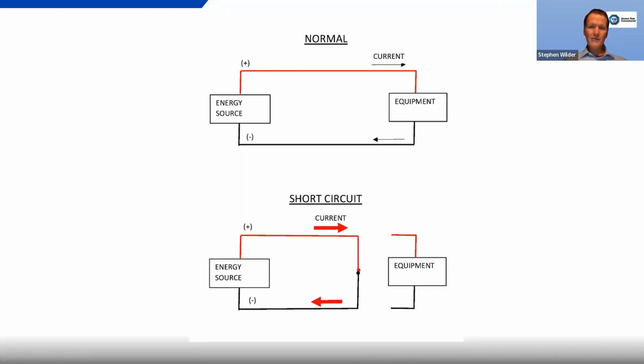Now, if the electrical system is designed properly, there's a circuit breaker upstream of each cable that's designed to trip the circuit, or open the circuit, before that energy is transferred into the wires. But that's not really what a short circuit study is about, technically. Each breaker has two ratings. There's a trip rating and an interrupt rating. The trip rating is what we normally refer to when we talk about circuit breakers. When we talk about a 20 amp breaker, that means if you put more than 20 amps on it, the breaker will trip. Most people understand that.